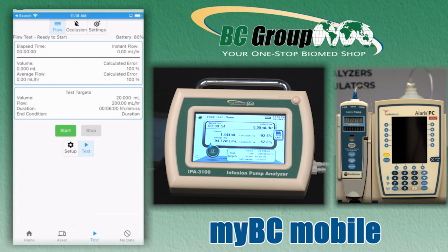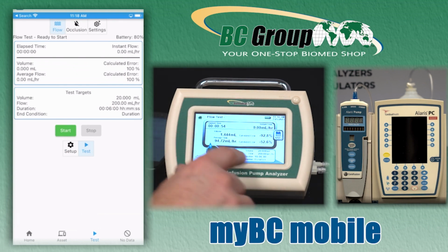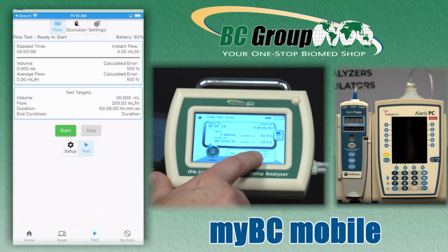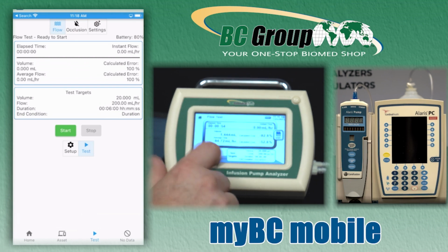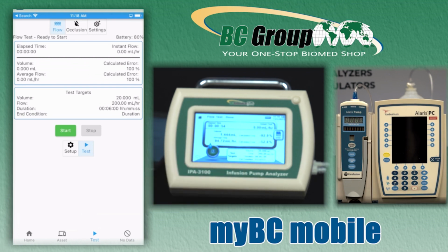So now in myBC Mobile, the test is configured. We can see on the screen, it's showing me the results of the previous test because I haven't started this one yet. But at the bottom, we can see targets. So the targets for the test are 200 milliliters per hour for 20 milliliter delivery, and it should be a 6-minute test, and it's set for duration as the end condition. So when I hit start, the meter is ready to measure. As soon as I start the pump, it's going to start measuring.